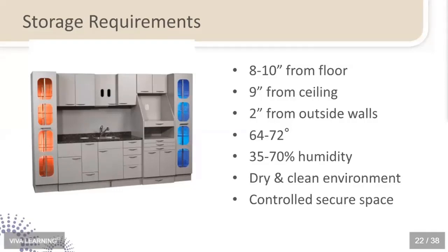This environmental guideline is from the AAMI Standard 79, not from our CDC guidelines at this point. I'm sharing this because these type of requirements are coming in dentistry - we're already seeing it in Canada. So I'm giving you a heads up of things you may want to look at in your own sterilization center, wherever you're storing instruments, to see if you're meeting these specific criteria. It's got to be 8 to 10 inches off the floor.